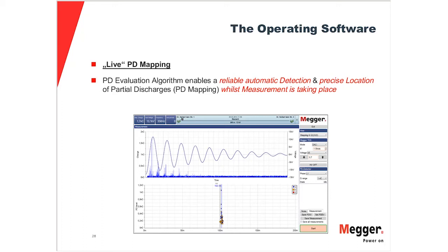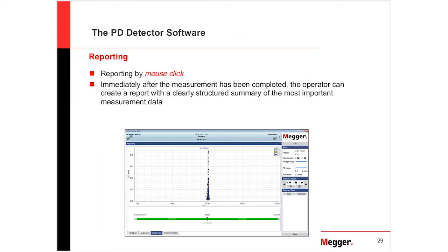In this example, we have a very short circuit of about 200 meters, and the problem is at around 100 meters. So there's absolutely no need for interpretation or evaluation. Everyone who can do the connection can run the test and see where the problem is, and depending on the severity of the problem, you then need to take action. But most important, you don't need to be the expert, it is built into our system.